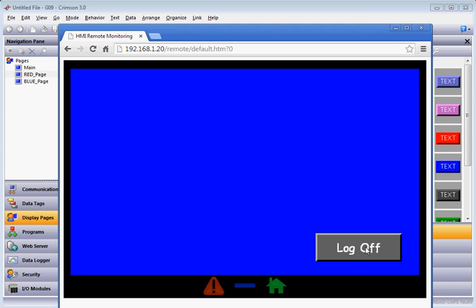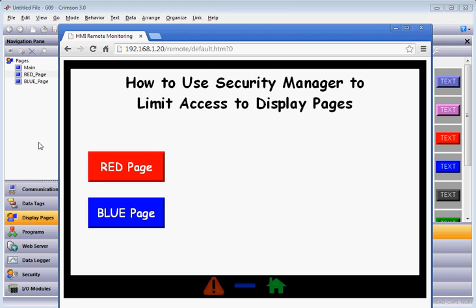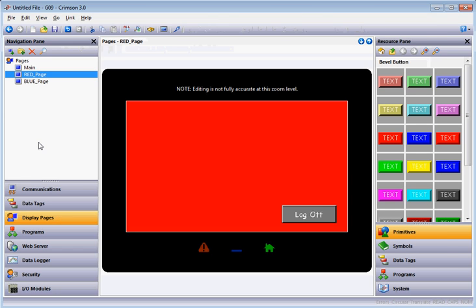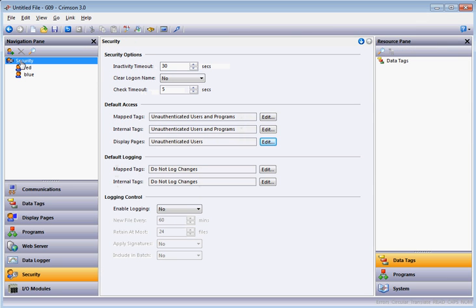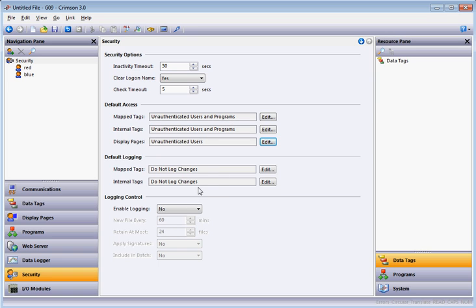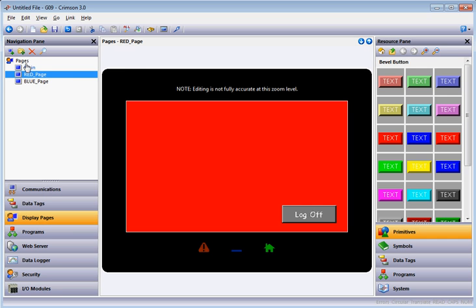If I hit Log Off I return back to the main page. A couple more things to show with the Security Manager — if you click on the main Security section, you can set an Inactivity Timeout to a longer or shorter time, which will automatically log the user out. The Clear Login Name option will remove the last logged-in username. You can also log who actually logged in and track changes.